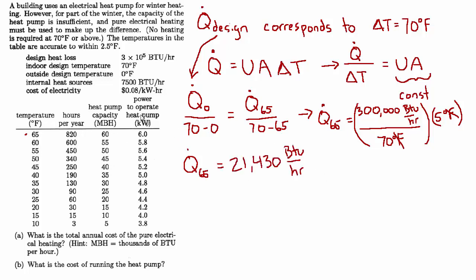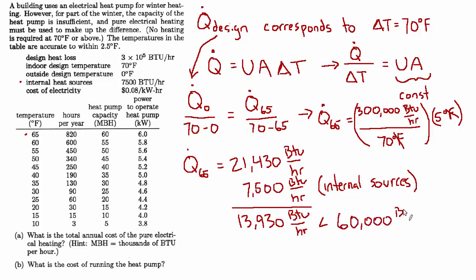And now we'll set that equal to any other ratio of heat loss divided by delta T. So we'll use q at T equals 65 outside, which we would like to know, divided by the corresponding delta T, which is 70 minus 65. And now we can solve for q_65. q_65 equals q_0, the design heat loss, 300,000 BTU per hour, divided by 70 degrees Fahrenheit, times this delta T, which is 5 degrees Fahrenheit. And that equals 21,430 BTUs per hour. Now some of that heat doesn't have to come from the heating system. Some of it's going to come from these internal heat sources.